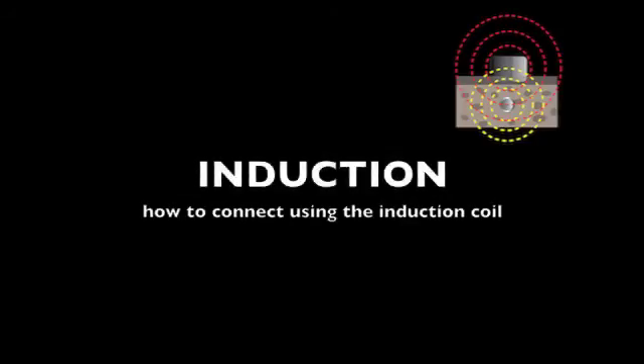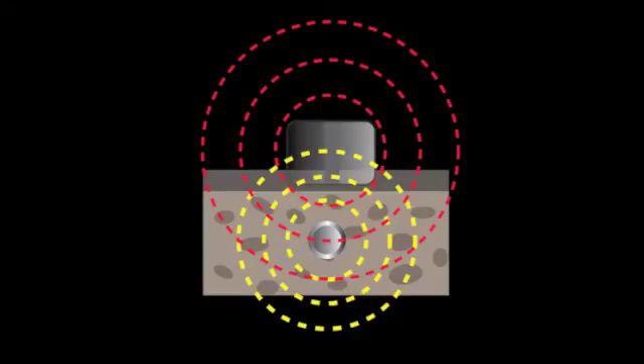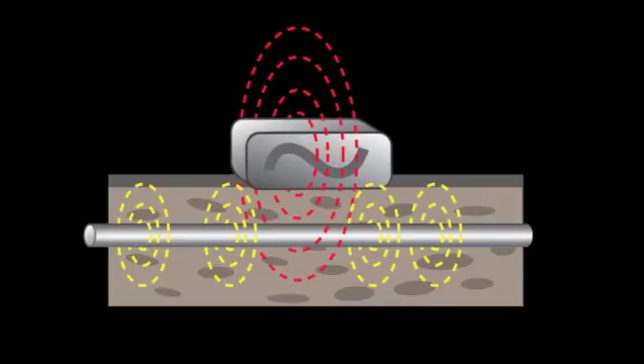The third way to connect the transmitter is using its induction coil, located on the bottom of the transmitter box. This method allows a signal to be applied without access to the line. Placing the transmitter on the ground, with the handle aligned with the utility, will induce a current on that nearby line.